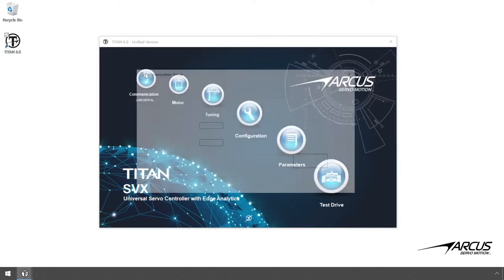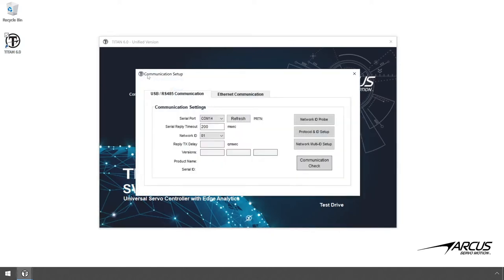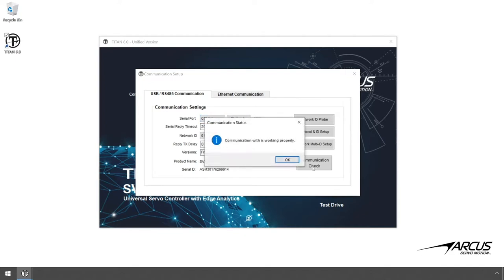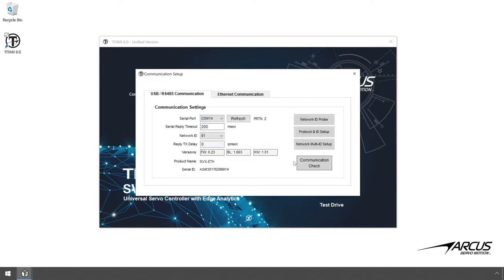Open up the Titan software. Open the communication window in the software and then click on the USB/RS-485 tab. Select the com port of the USB/RS-485 converter, click on the check com, and confirm that the communication is working properly. You can try going to other screens and confirm the communication is working properly.